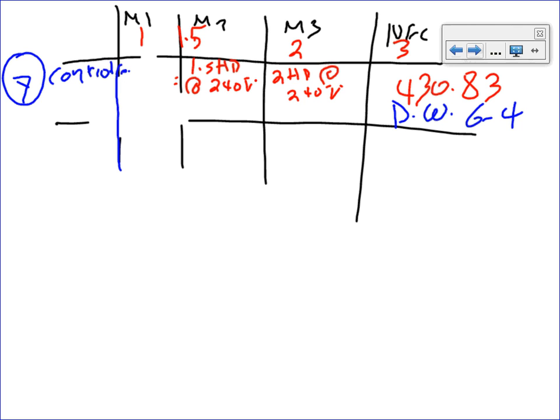So this is going to be 1 horsepower at 240 volt, and the NEMA for this, let's use this, the NEMA for it is going to be NEMA 00. Okay, let's look at the second one, 1.5. Can I get NEMA 00 to get me up to 1.5? No, I exceed the 1, so I need to go to what NEMA? NEMA 1 can get me, so this will be NEMA 1.